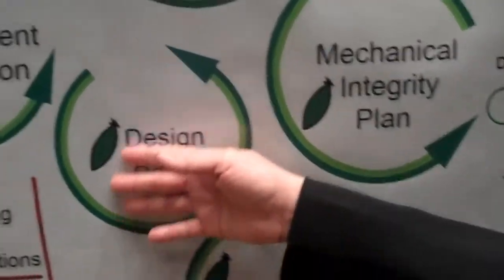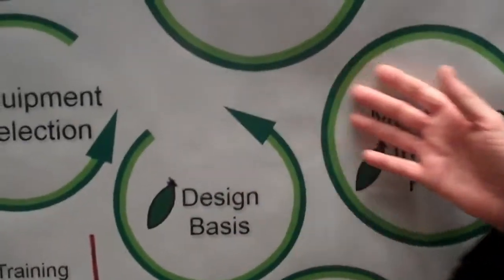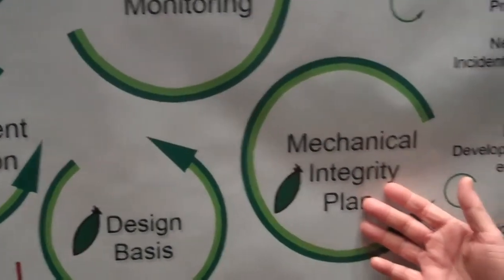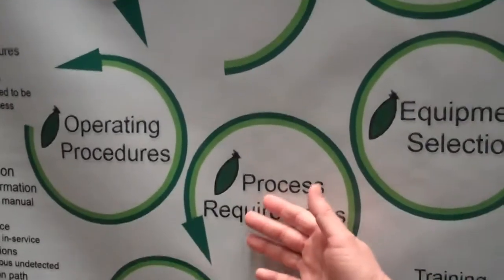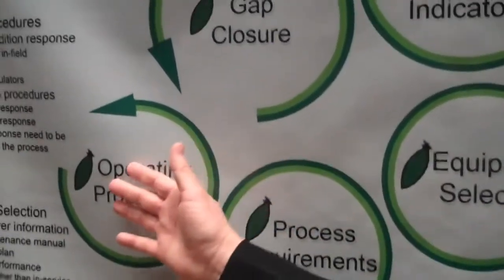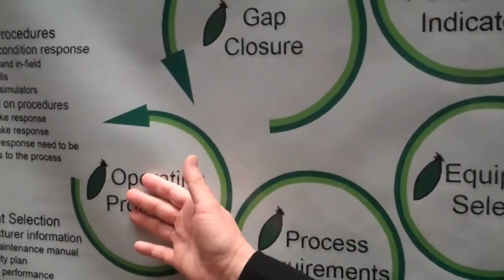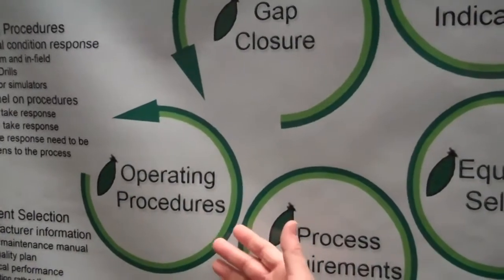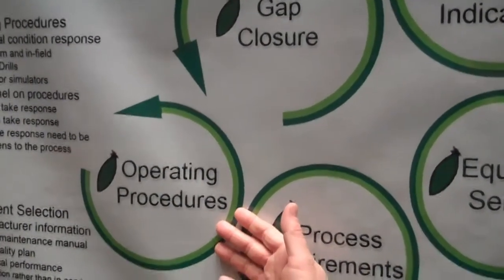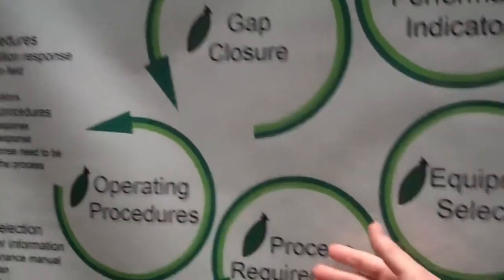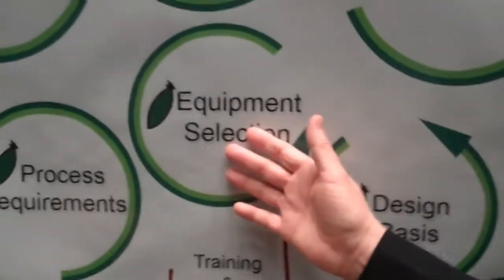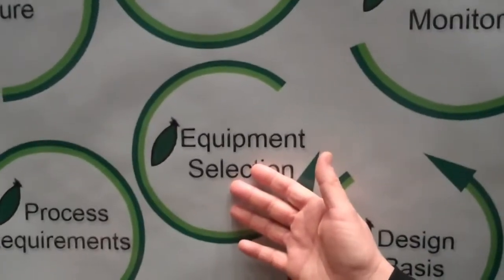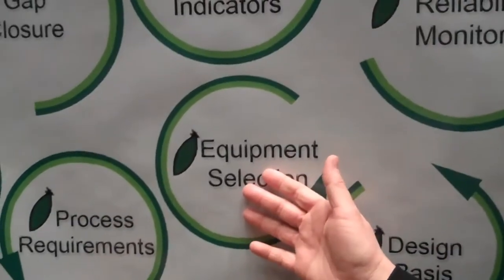From the performance verification to design basis, we develop our mechanical integrity plan on what's necessary to maintain the equipment. The hazard analysis that led to the process requirements yields operating procedures on how we cover safe automation and safe operation of the process. The process requirements in the design basis lead us into selecting equipment that we install and maintain according to the mechanical integrity program.